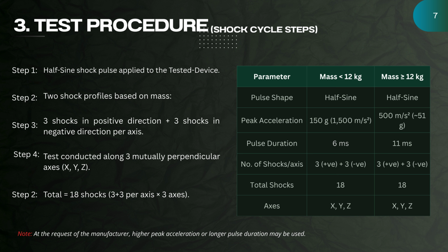The battery gets 3 shocks in the positive direction and 3 in the negative direction for each of the 3 axes, X, Y, and Z. That gives you 18 shocks in total. This makes sure the pack is tested from every direction. Higher acceleration or longer pulse duration can be requested by the manufacturer if needed.